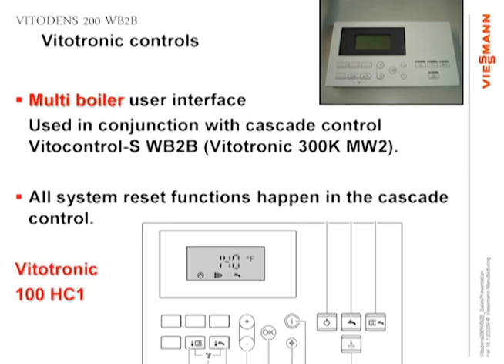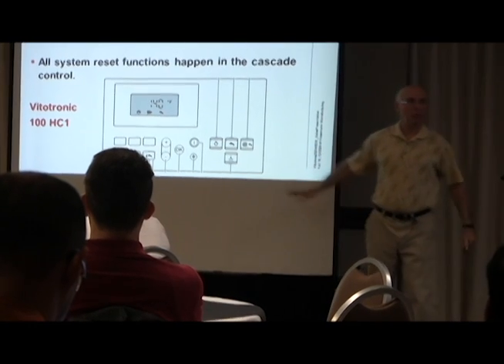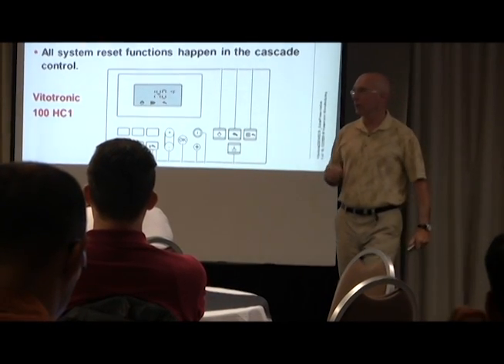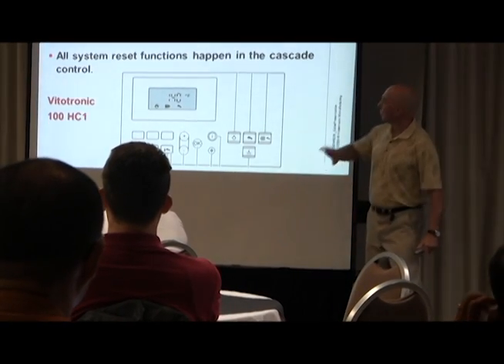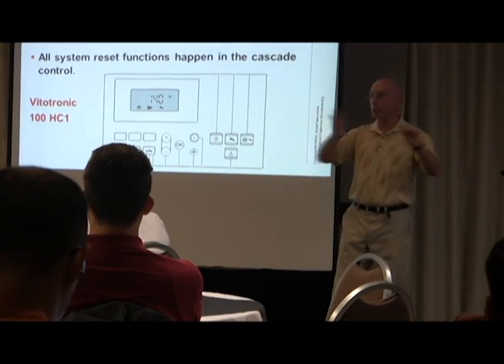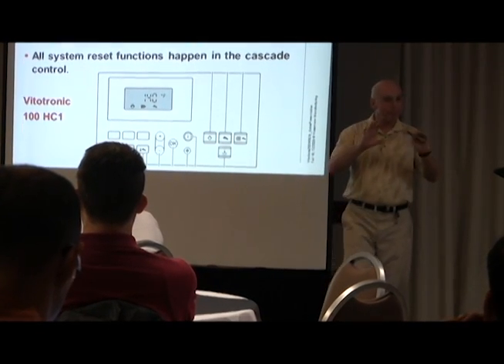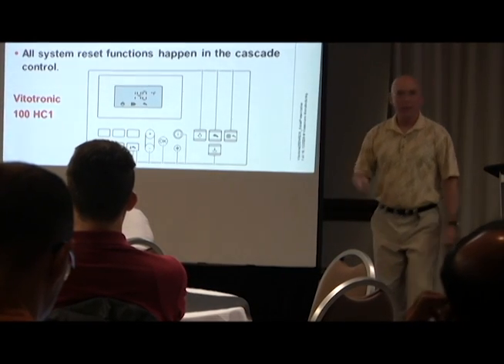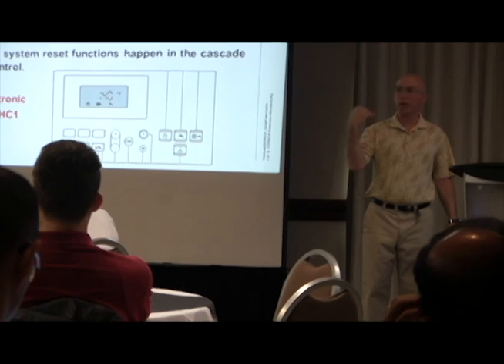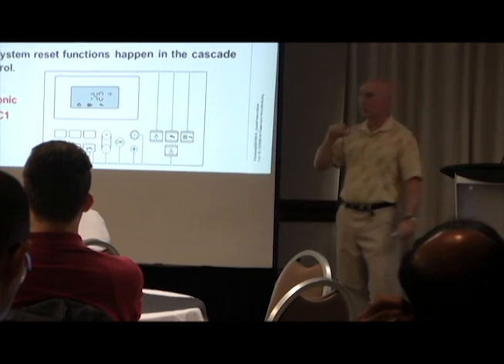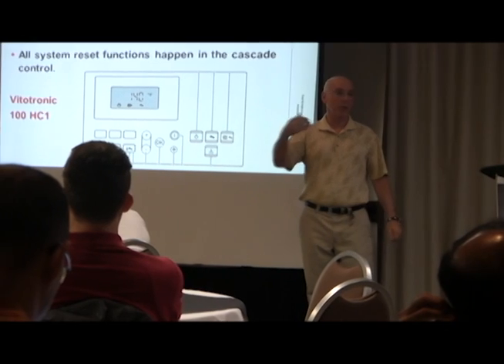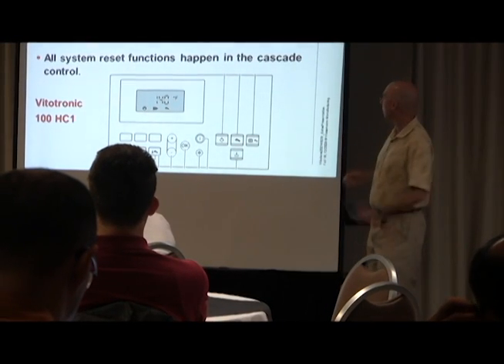One thing we have to be careful with when ordering is that Viessmann recognized maybe you don't want our control, maybe you want a third-party control. If that happens, there's a control in each individual boiler that has to be matched up to whatever third-party controller you're using. So it's a question I'd ask from a sales perspective, in terms of what you need in the field and how you're going to control it. That's something we'd go over as we go along.